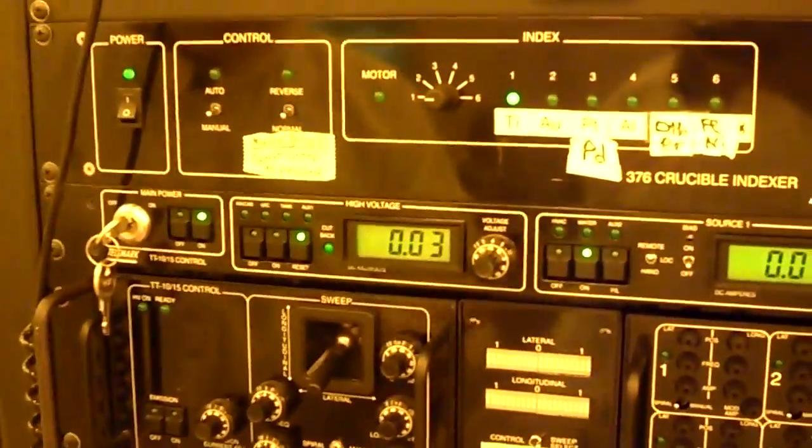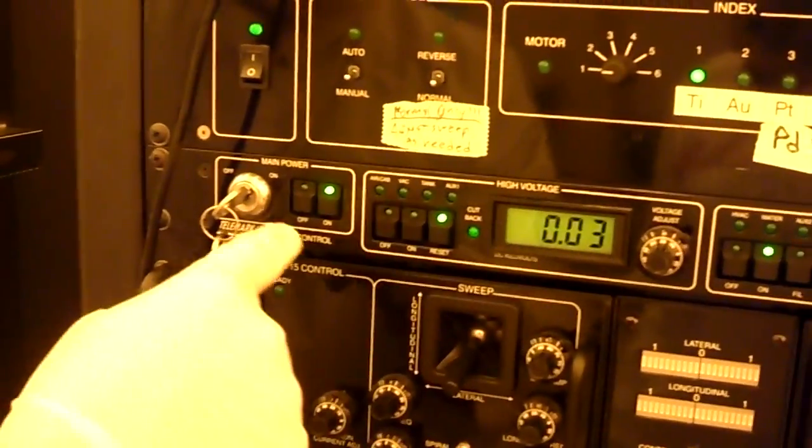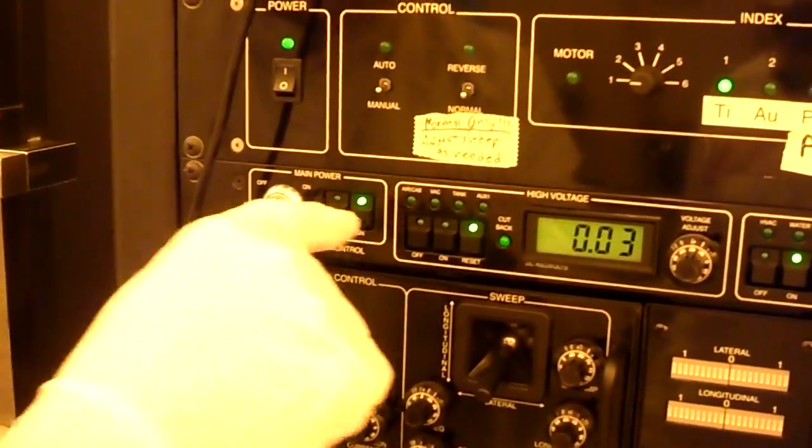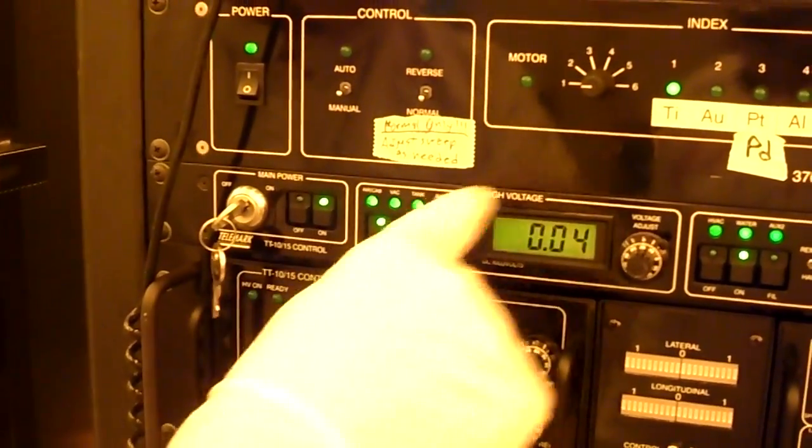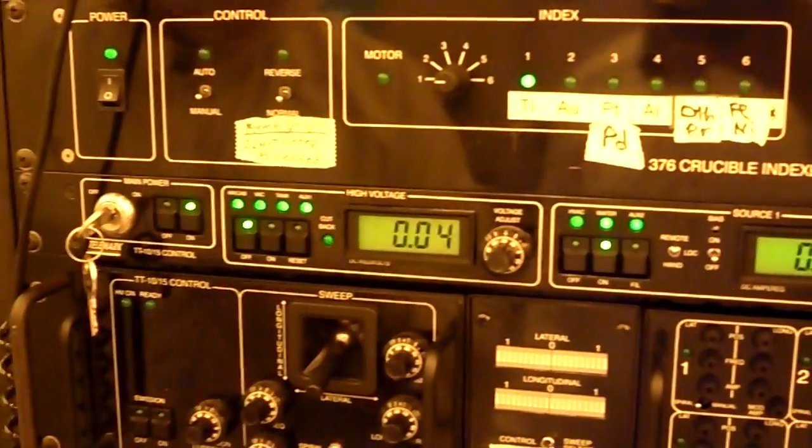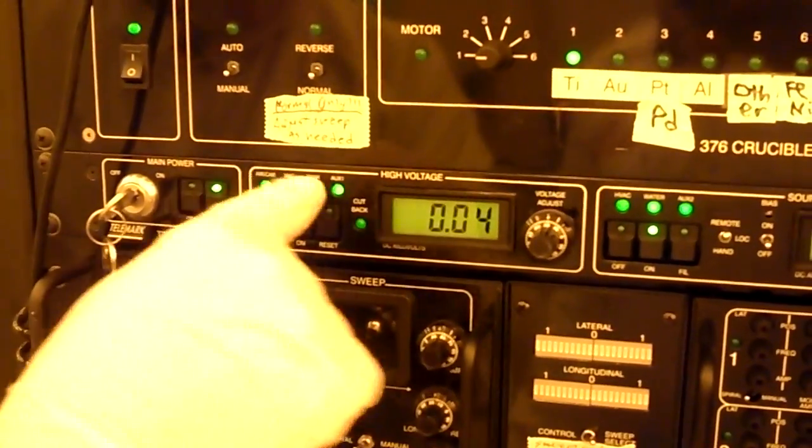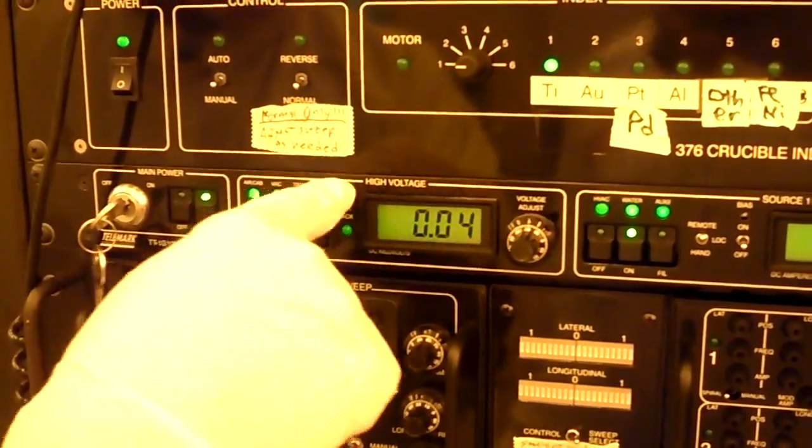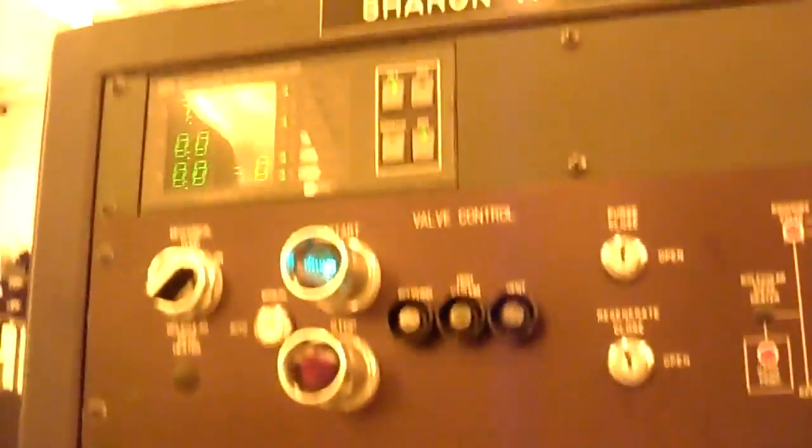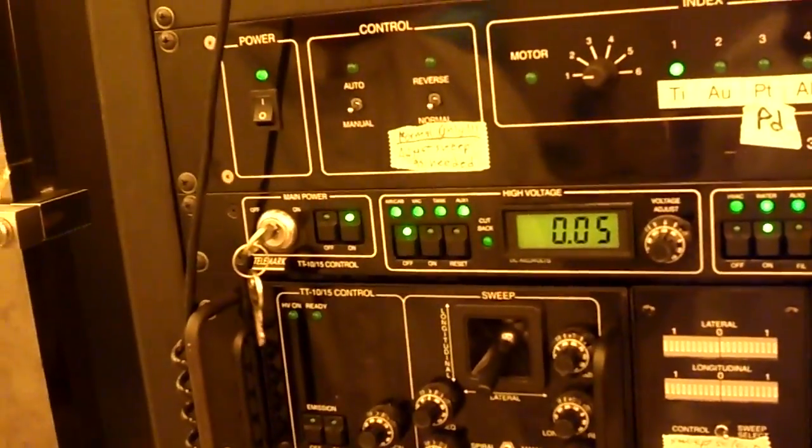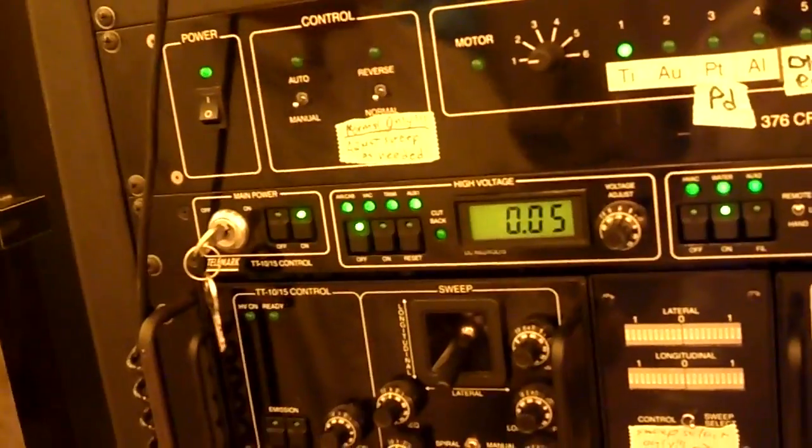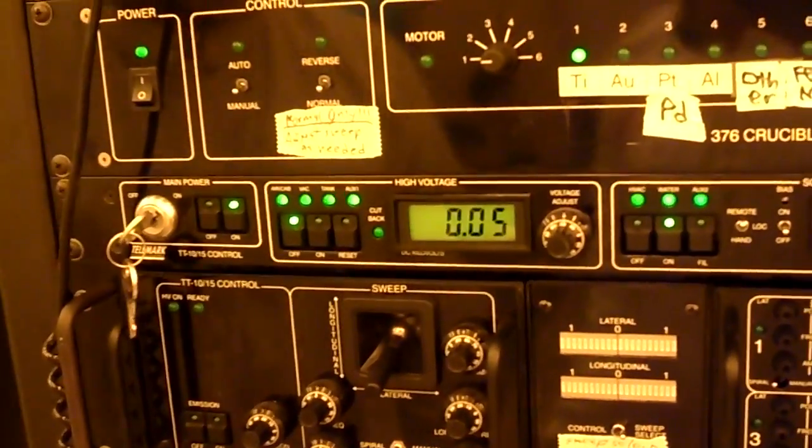All right, so the next thing is we actually turn the high voltage part on, which we do. We've gone on, on, on, reset, and what that does is that checks all of the safeties. Water is flowing. Air is flowing where it ought to. The vacuum is good enough. If the vacuum gets above about 5 times 10 to the minus 5, the high voltage will cut out, because you might be vented or something, in which case it shouldn't be running.